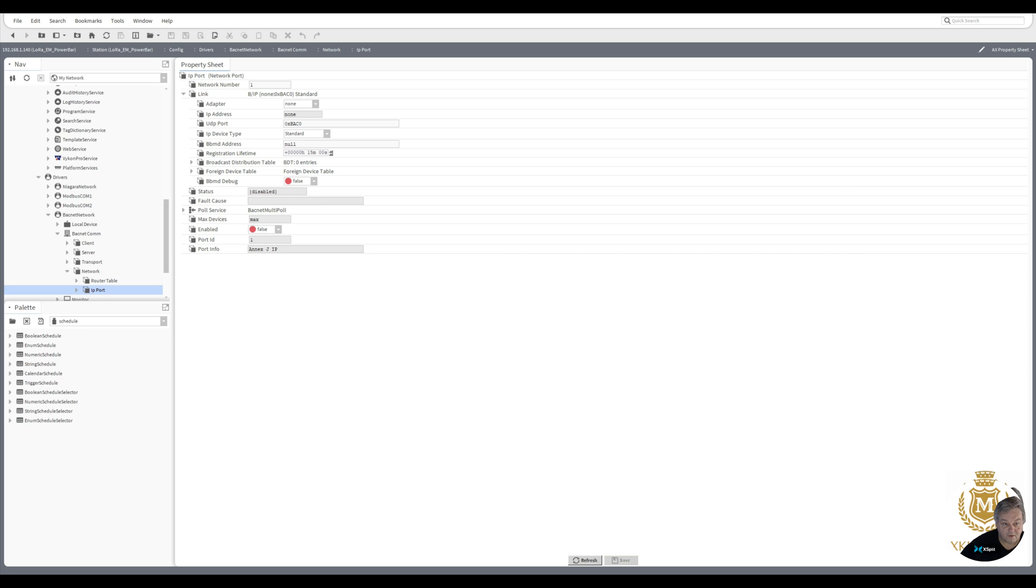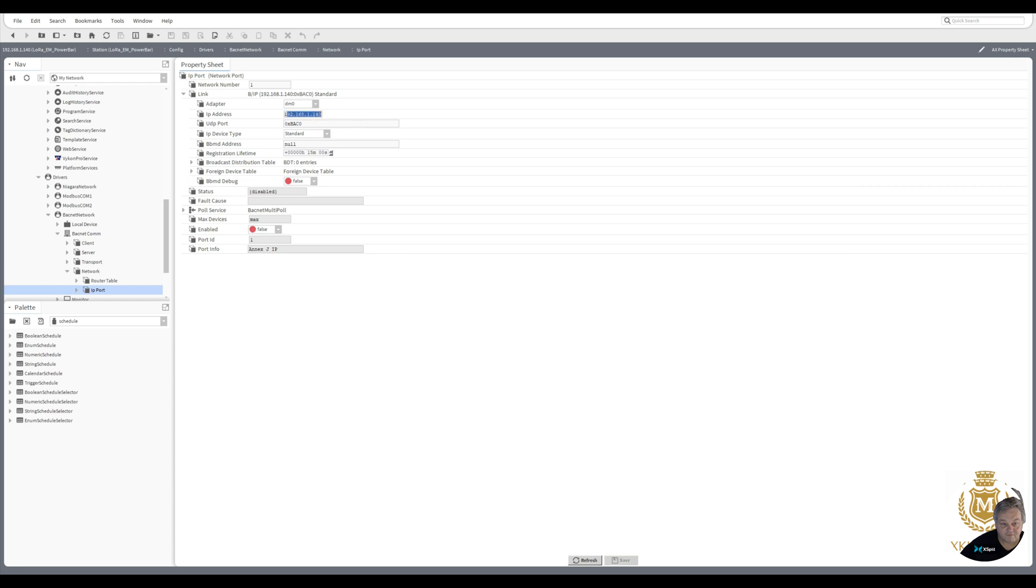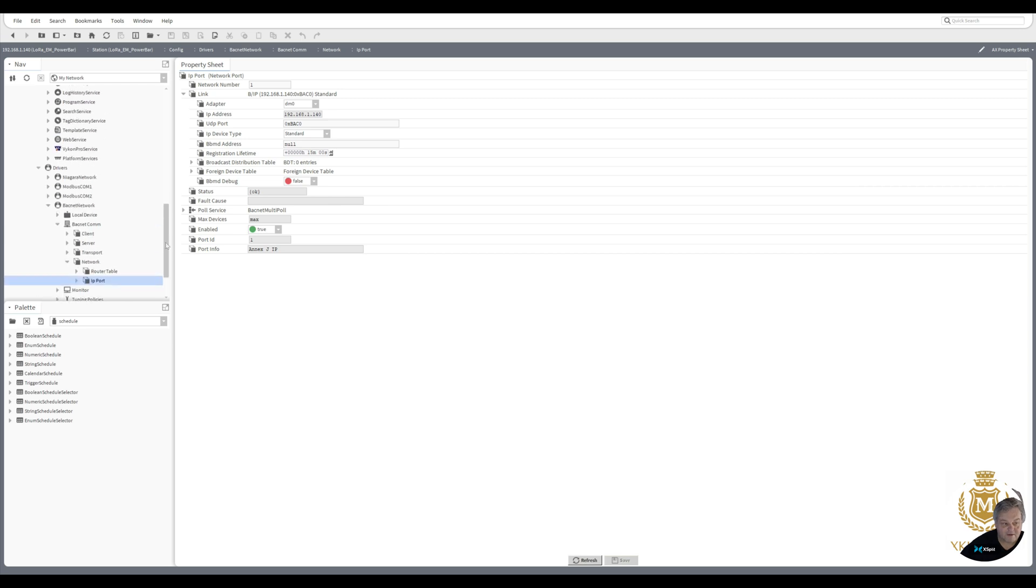Now we've got the BACnet comms here and network. You see you've got IP there, so that's on network number one. We've got to pick an adapter because this is an IP. Out of the two adapters that we've got, we've got to pick an adapter. So if I pick adapter D0 and save that, that comes up of my IP address of the system that D0 is connected to. At the moment it's still saying disabled there, so if I right-click that IP and enable, that's now enabled. So that's your IP done, your Ethernet IP for your BACnet.